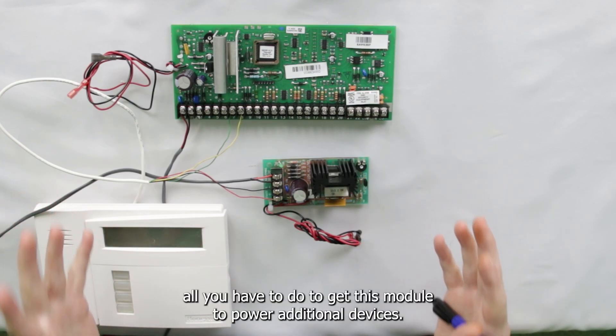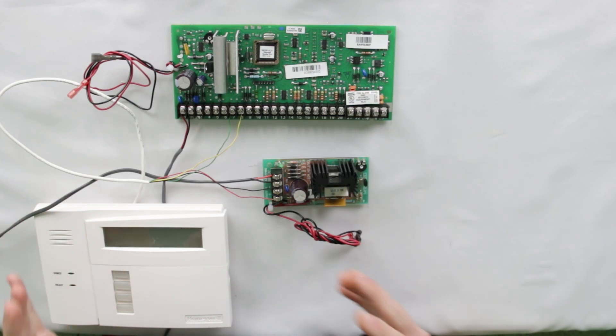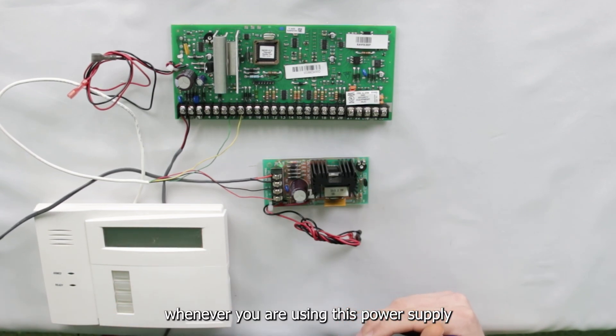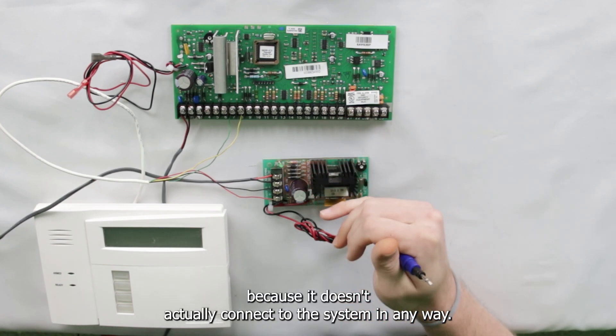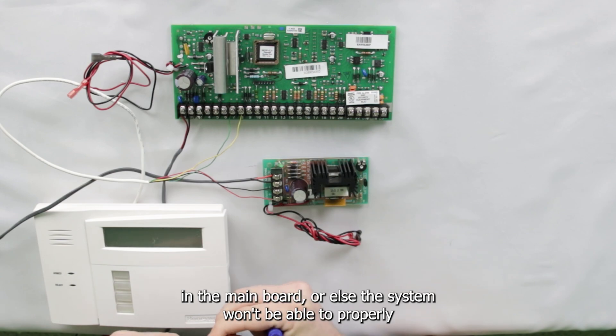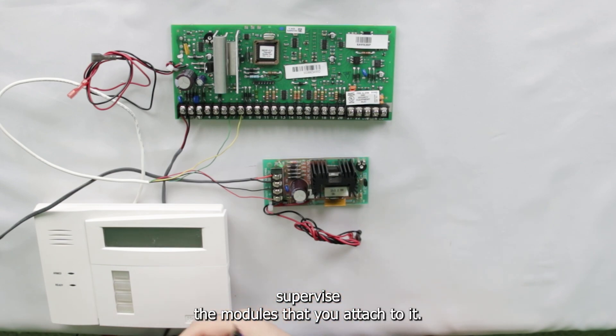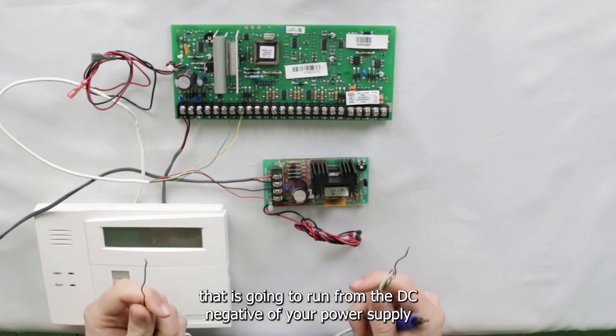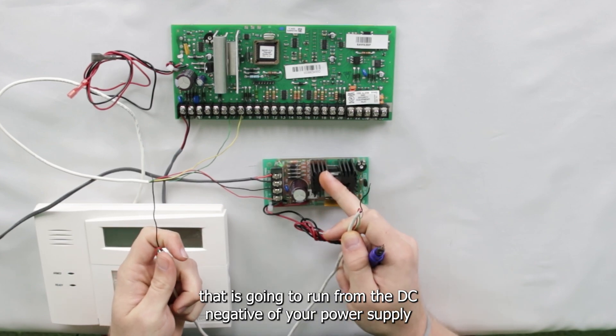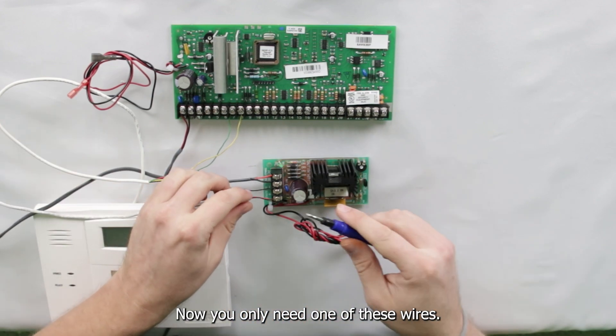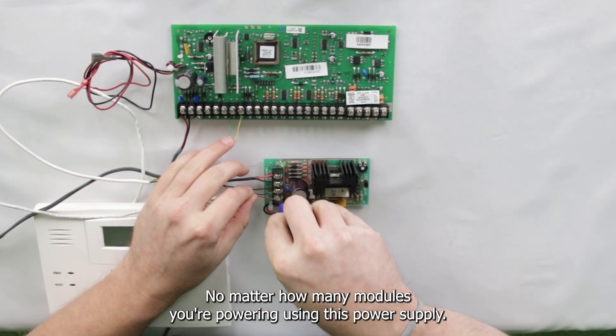And that's literally all you have to do to get this module to power additional devices. However, there is one additional wire that you have to use. Whenever you're using this power supply, because it doesn't actually connect to the system in any way, you have to connect the grounds between the power supply and the main board, or else the system won't be able to properly supervise the modules that you attach to it. So essentially, you need one wire that is going to run from the DC negative of your power supply up to the number four terminal on your main board. Now you only need one of these wires no matter how many modules you're powering using this power supply.